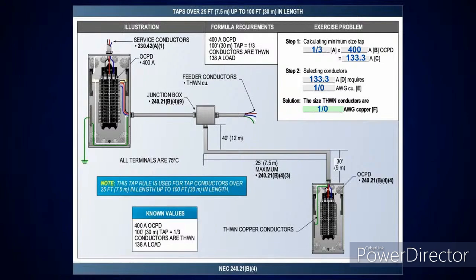That gives you 133.3. In this case, we're doing copper. So I'll go to table 310.16, 75 degrees C column. The next size above the 133.3 is 150. Come across. It's going to tell you that the size THWN copper conductors are required to be 1/0. Simple. And if you notice, I didn't change anything. I stayed the same process all the way through. I took a third for everything that was over 10 foot. The only difference I did was on the secondary of a transformer that's in a tap. I took the ratio of the transformer part of that calculation.